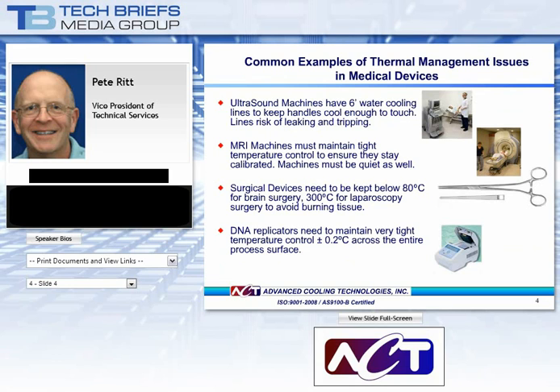Here are some examples of thermal management issues in medical devices that we've come across. Undoubtedly, there are many others. Some ultrasound machines have 6 feet of water cooling lines to keep the handle cool enough to touch. The 6 feet of cabling can be a safety factor for both the patient and the operator in terms of tripping and leaking, not to mention skin irritation that may occur if the pumping malfunctions. MRI machines must hold tight temperature control to maintain calibration. There are lots of options for thermal management, but when adding the extra requirement of quiet operation, solutions other than pumps and fans may need to be implemented.